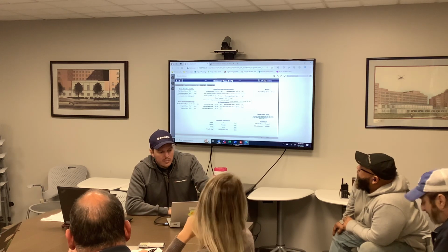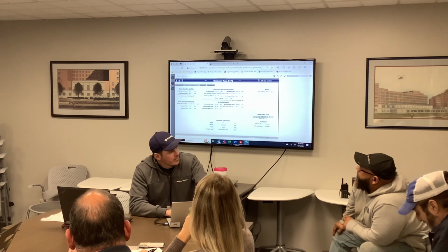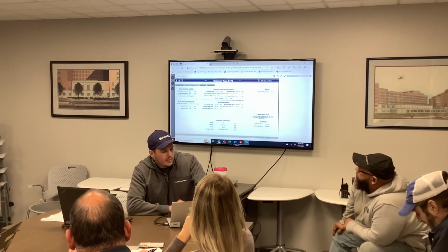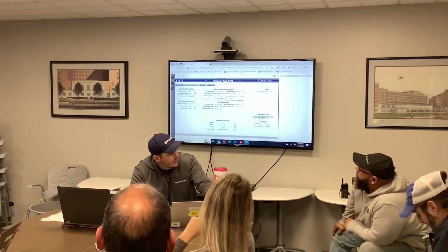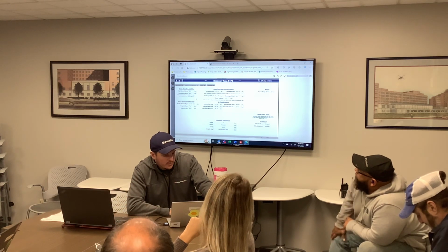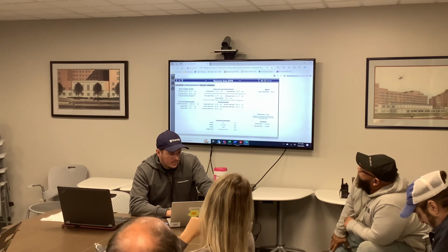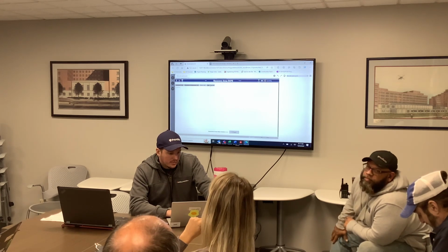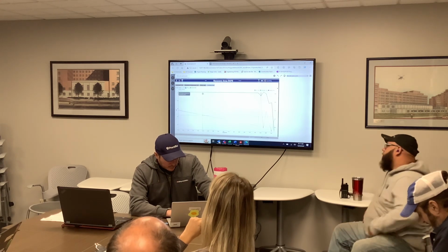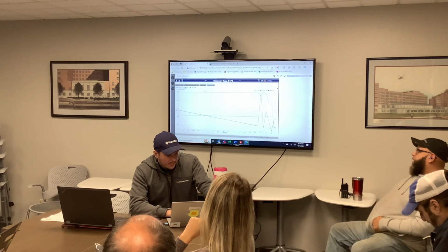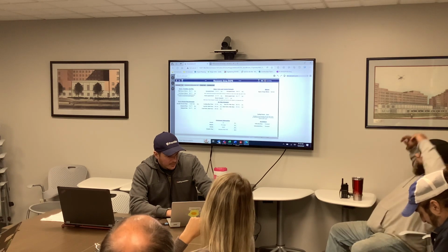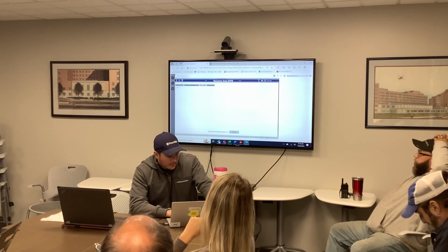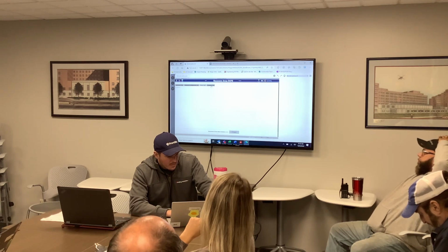What about the alarm trigger set points? Are those adjustable? Yep, those are adjustable, because we probably want to see it sooner than 85 and sooner than 60. I don't think so, if they're doing night setback at 80, you have alarms all night long. I was thinking like 65 and 80. Having that trend there is pretty useful when you aren't in the room doing all that research. You definitely want to go above the night setback temps. Yeah, I forgot about that.